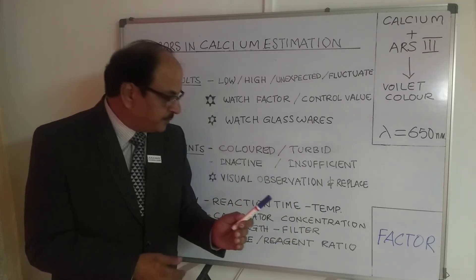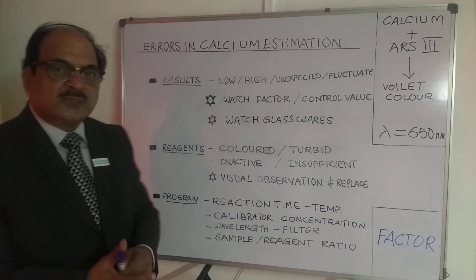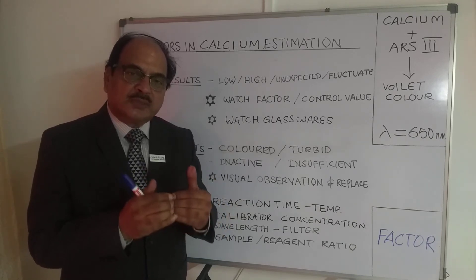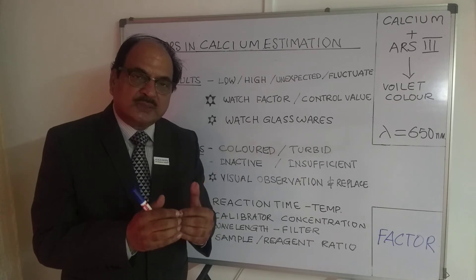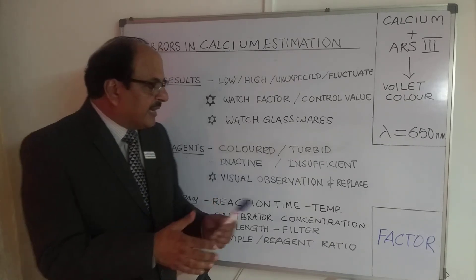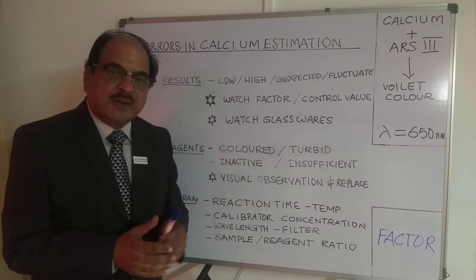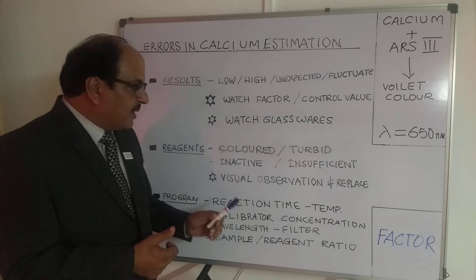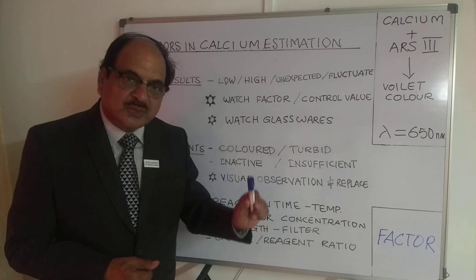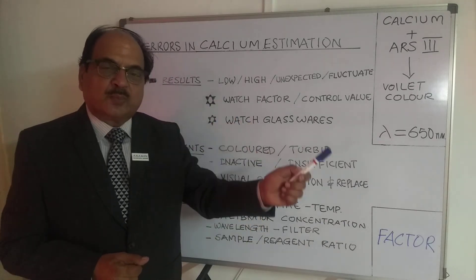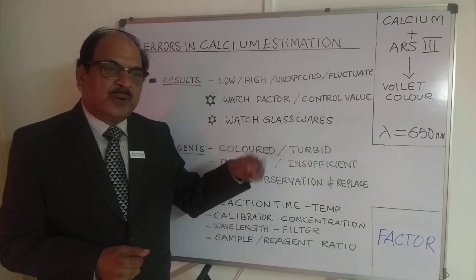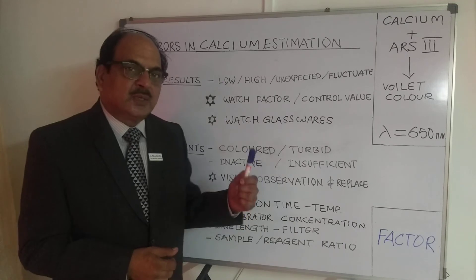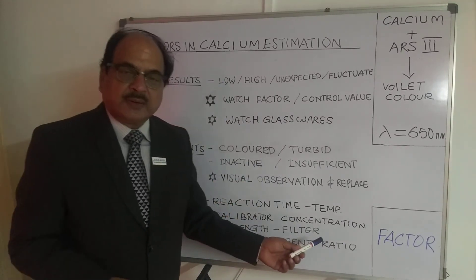Calibrator concentration is another very common source of error. The calibrator is a lyophilized or liquid serum from a third party with a value that is lot-specific and reconstitution-date specific. Calcium is more or less a stable compound, but it is recommended to continue in the same calibration cycle once you begin your first aliquot or reconstitution. Critically, ensure that the lot-specific value from the current vial is entered into the program — very often the previous vial's value is fed in while running calibration with a new one, which is bound to give wrong results.